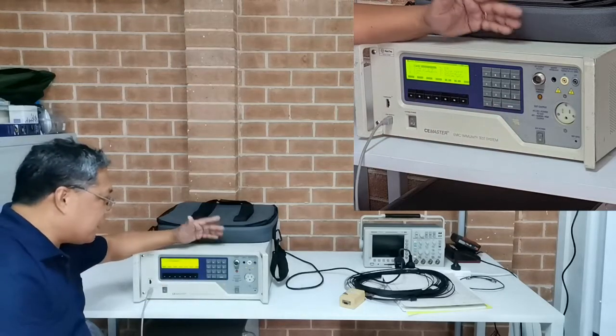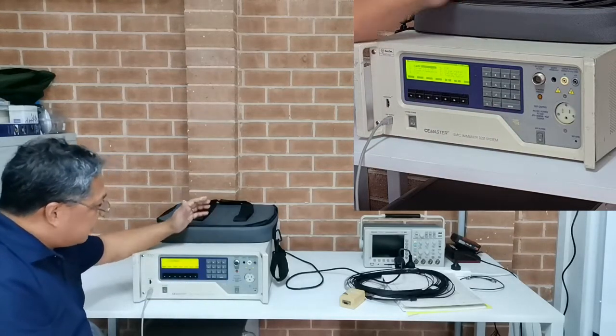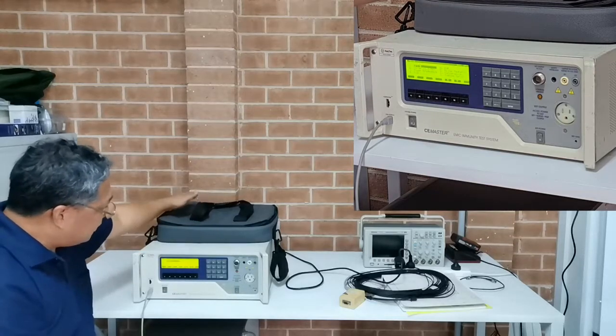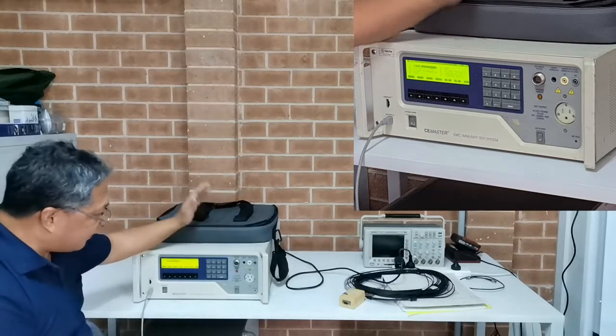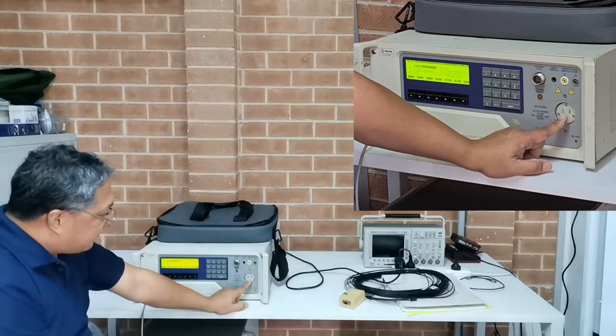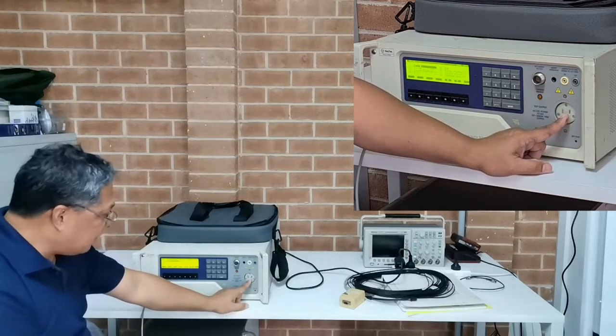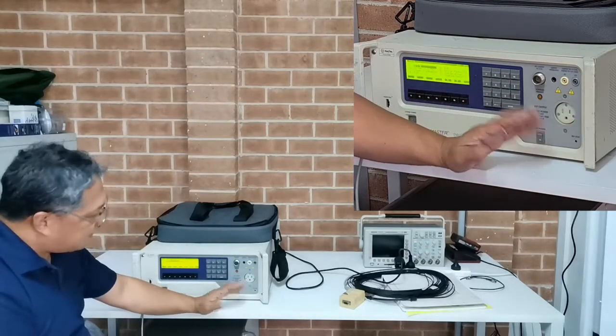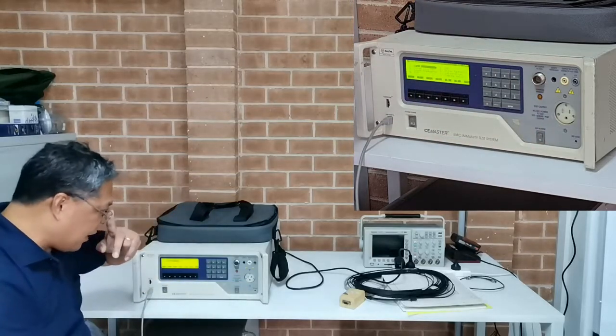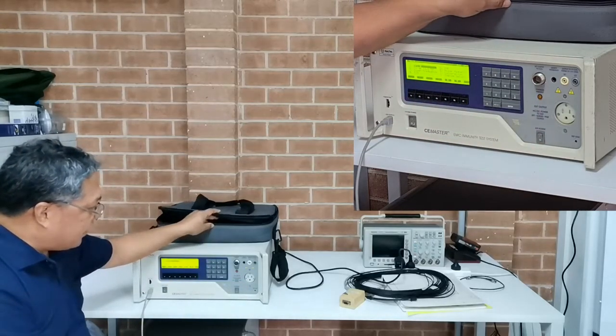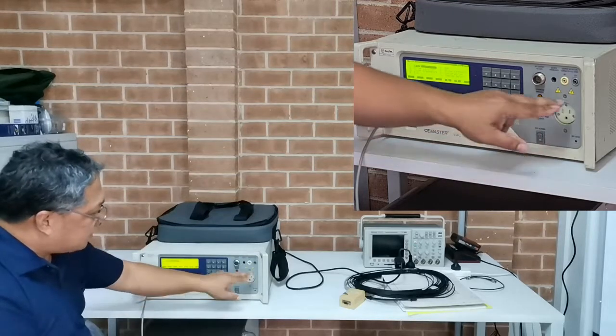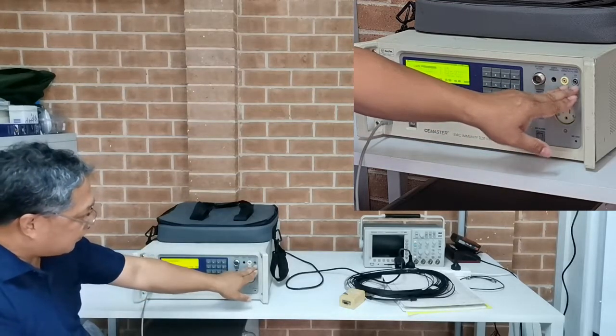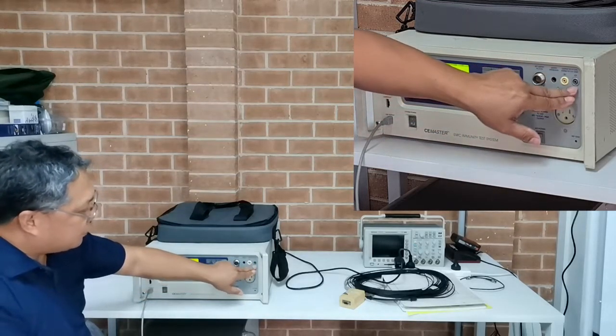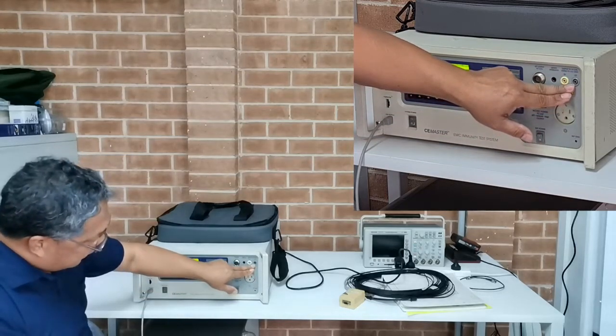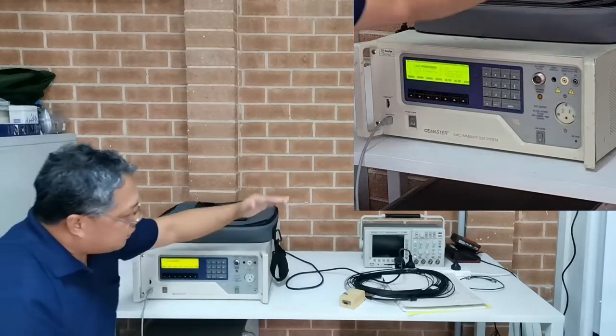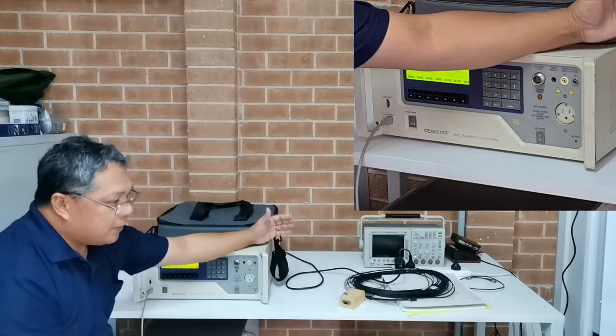First thing is, before I do the surge, you have to power the EUT, and the maximum voltage is only 125 volts. The output here is where you plug in the EUT and apply the surge. But the maximum input voltage is only 125 volts, so we can't really do it. So the best option is to use a direct output from the high and low surge test.